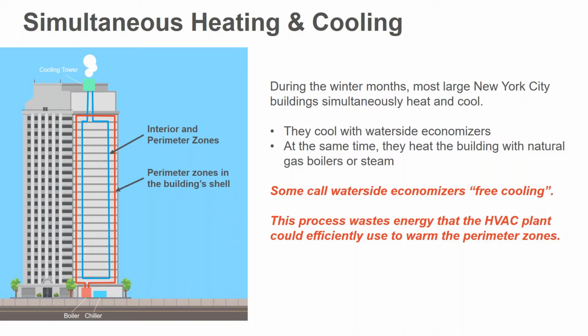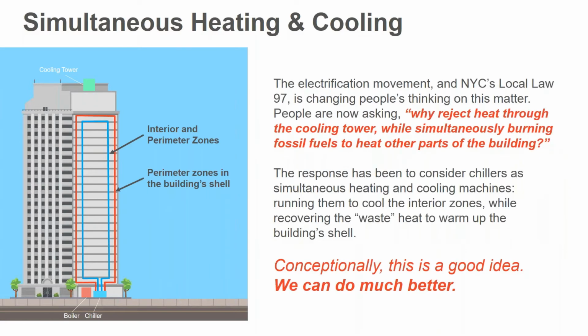Well, if you look at this from an energy point of view, this is throwing away energy, right? You've got too much energy in the core of the building. It gets too warm, and so we just throw that energy away to the atmosphere, okay? Well, Local Law 97 is forcing us to think about heat pumps and electrification. And so obviously the first thought is, why would you reject this energy when there is simultaneous heating and cooling going on in a building? So in the dead of winter, when the core is overheating, but you still need heat in the perimeter of the building, why aren't you just heat pumping it and running a chiller and having the heat from the condenser of the chiller go to the skin of the building? So, a very good idea. It certainly works, and we're moving in this direction as we're designing new buildings. It makes a total amount of sense.